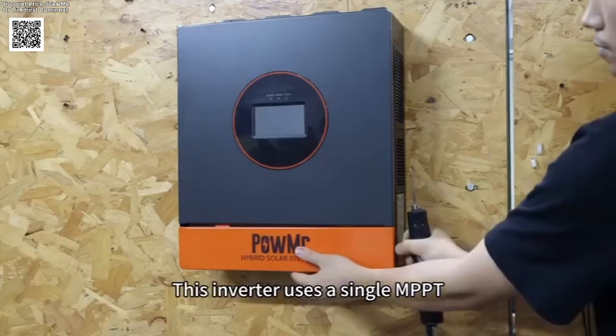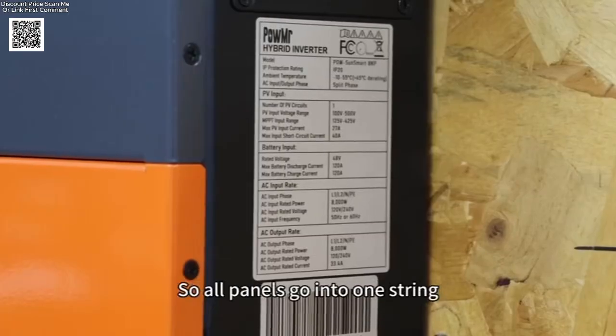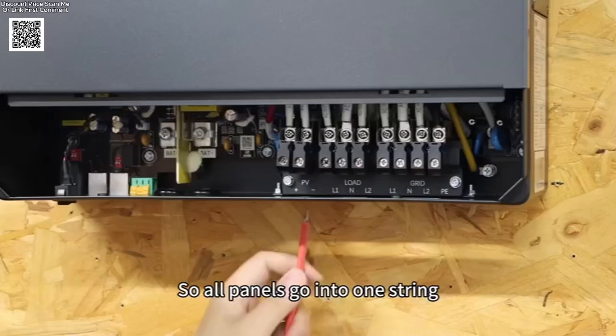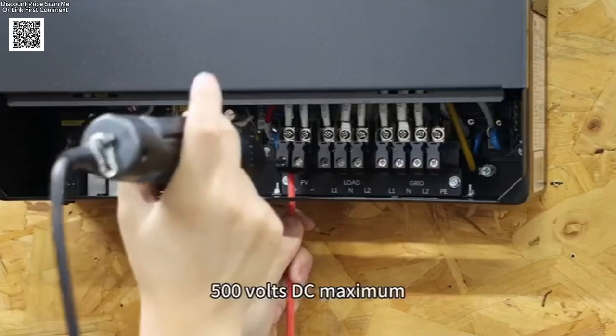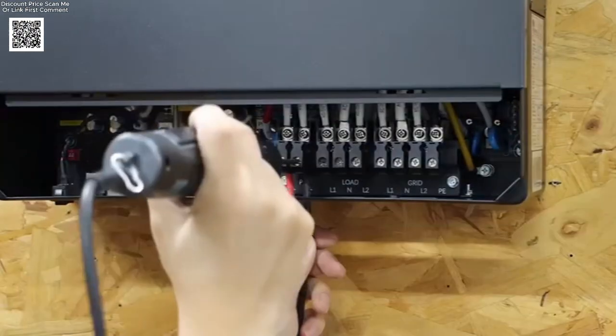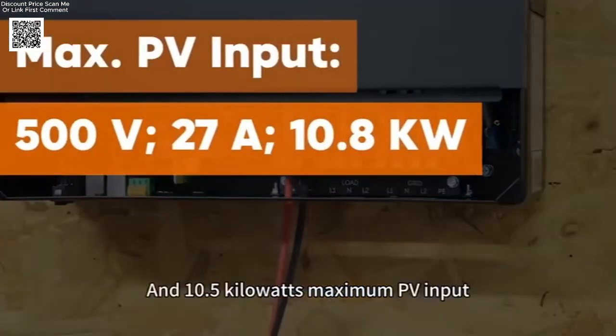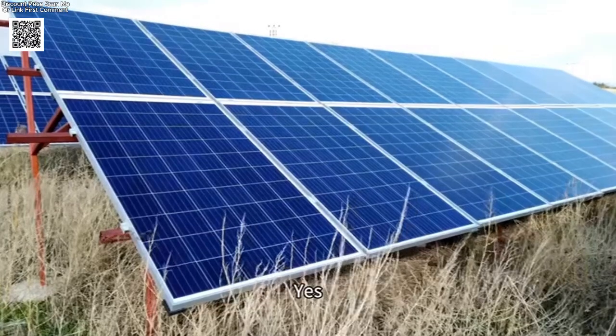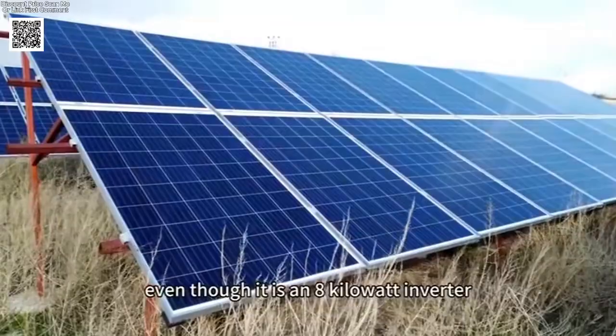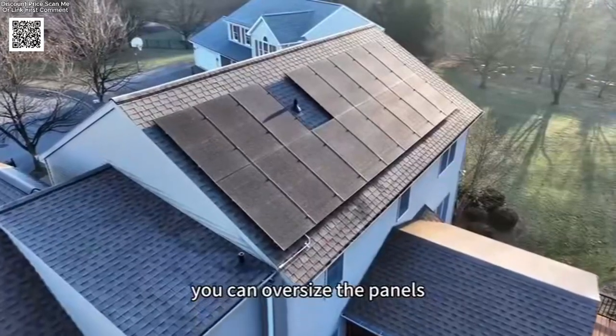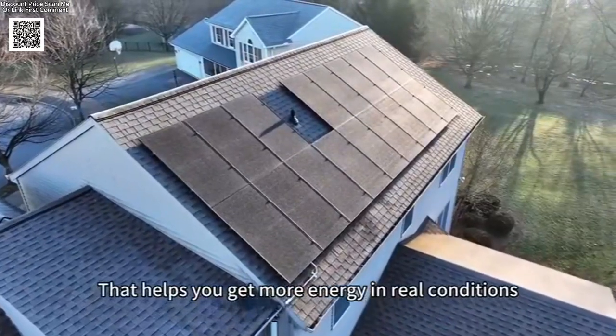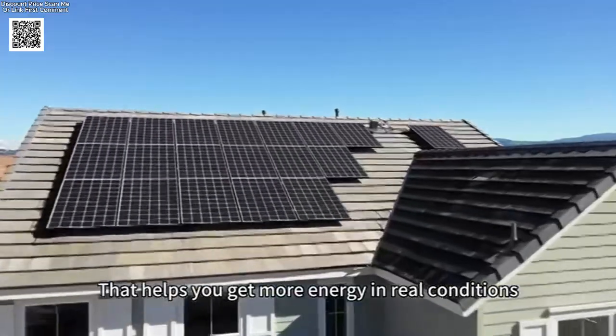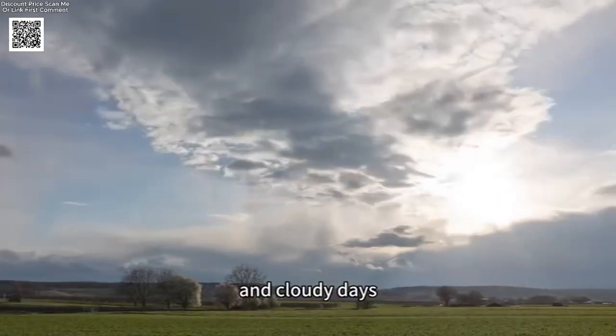This inverter uses a single MPPT, so all panels go into one string. Limits are 500 volts DC maximum, 27 amperes maximum, and 10.5 kilowatts maximum PV input. Yes, even though it's an 8 kilowatt inverter, you can oversize the panels. That helps you get more energy in real conditions, morning and cloudy days.